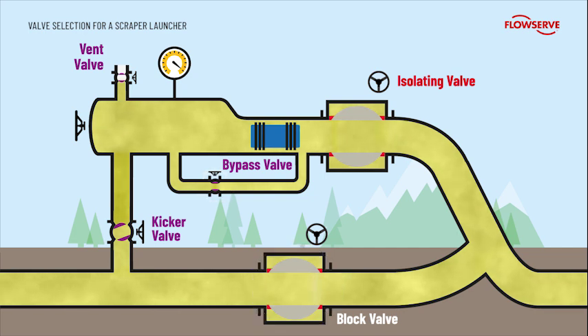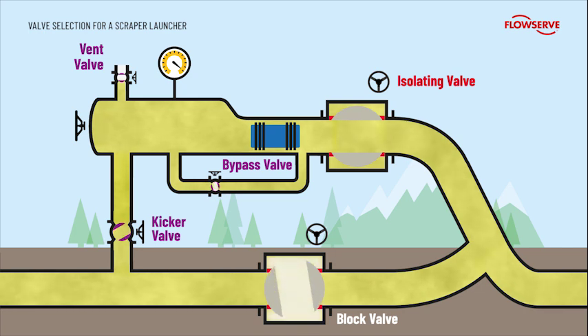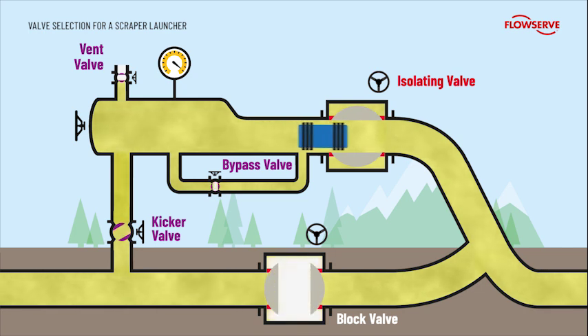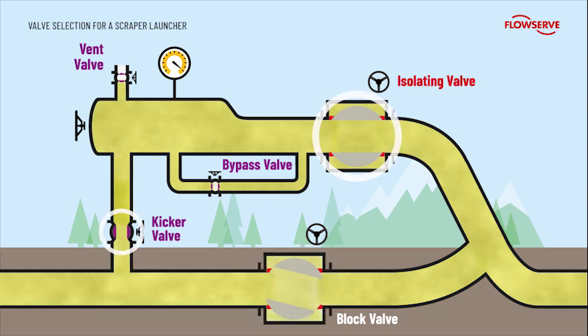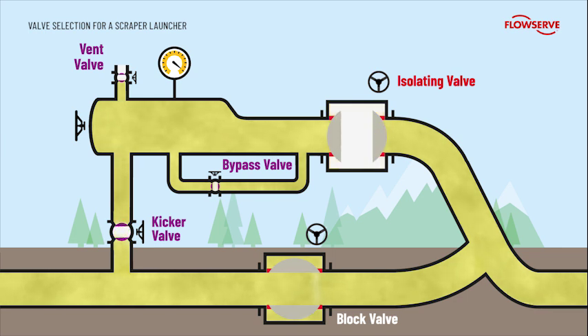The bypass and block valves are now closed. This generates a gas flow behind the scraper, launching it into the pipeline. Once the scraper has moved down the pipeline, the block valve is opened and the kicker and isolating valves are now closed. The launcher is now isolated and returned to its original position.